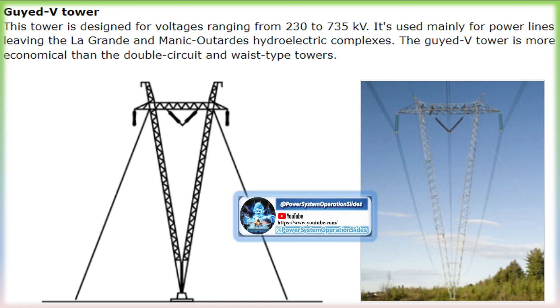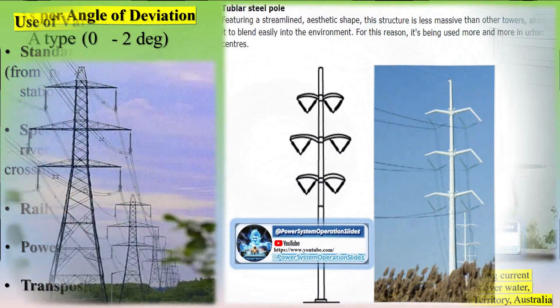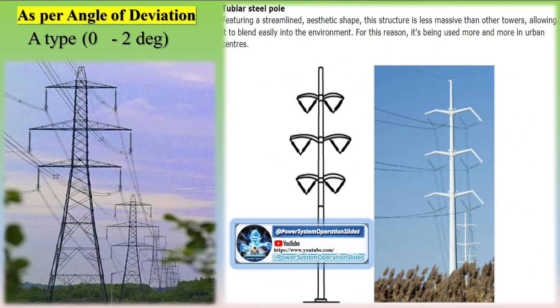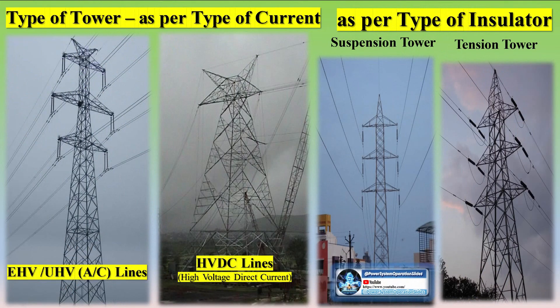The structures commonly used on transmission lines are either lattice type or pole type. Lattice structures are usually composed of steel angle sections, while poles can be wood, steel, or concrete. Each structure type may be self-supporting or guy-supported by cables. Pole type structures are generally used for voltages of 345 kV or less, while lattice steel structures are favored for higher voltage levels. Wood pole structures can be economically used for relatively short transmission distances and lower voltages.